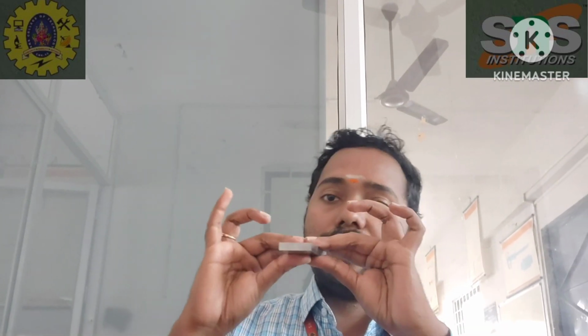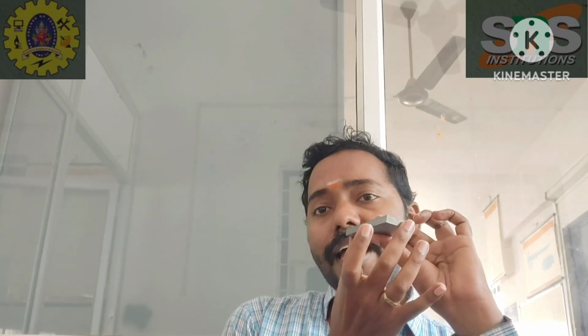In our lab, micrometers, vernier calipers and profile projectors, these small measuring instruments and equipment, will be calibrated using this type of slip gauge, because this is a standard gauge. This is equal to an international standard or national standard. The value between the two highly polished surfaces is what gives the 100 mm.